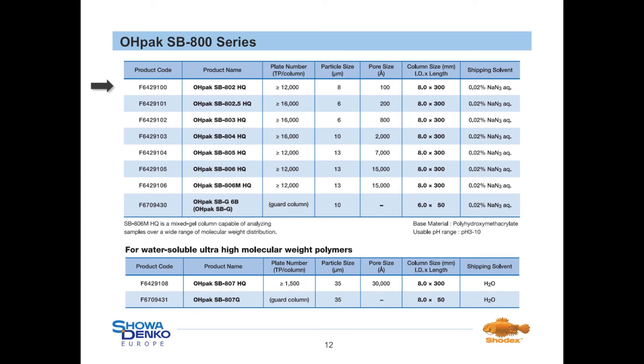The OH-PAC SB-800 column series offers a wider variety of pore sizes than the Protein KW column series. Therefore the SB-800 series can cover a broader molecular weight range. For example, the OH-PAC SB-802HQ column covers a low molecular weight range from 100 to 4,000 Dalton with a maximum pore size of 100 angstrom. In contrast, the OH-PAC SB-806HQ has a maximum pore size of 15,000 angstrom and is able to cover a range from 100,000 Dalton up to an estimated value of 20 million Dalton. For ultra-high molecular weight polymers, the use of the OH-PAC SB-807HQ is recommended. Beside single gel columns, also a mixed gel column can be offered. The OH-PAC SB-806M consists of different gels and therefore shows good linearity over a broad molecular weight range.